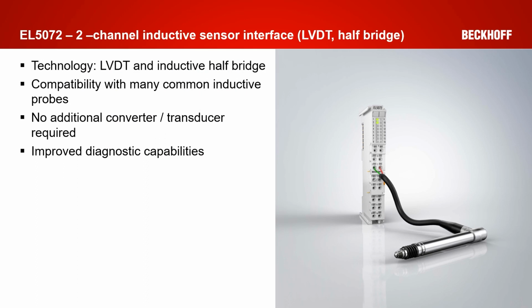What are the main key points of the EL5072? First, it's a two-channel solution and you can connect and evaluate two inductive sensors directly. The EL5072 supports full bridges in LVDT design, but also inductive half bridges. Due to different connection points and input impedances, you can connect almost all common sensors on the market. Therefore, you are really flexible in your design and can use the right sensor for your application. Furthermore, the advantage is that no additional converters or transducers are necessary for the use of LVDT sensors anymore. These black boxes are always expensive and additionally have negative influences on the accuracy due to the multiple signal conversion.